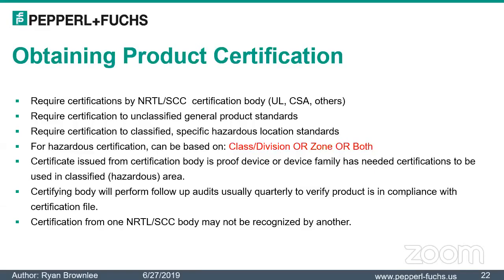Well, what are we seeing offshore these days? Is DNV still prevalent on that? Coast Guard, what are you seeing out there? So offshore is ATEX. You're talking about on a rig? It's IECEx. It was ATEX a few years ago that was prevalent. They would allow some Class Div, but that was almost 3.5 to 4 years ago. They changed, and now IECEx is the official certification required for everything on Gulf of Mexico offshore rigs. And there are some legacy platforms that of course still use Class Division.